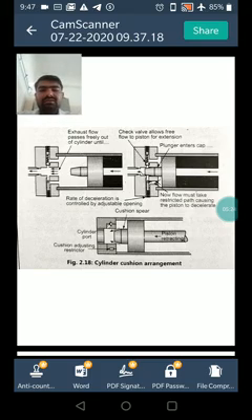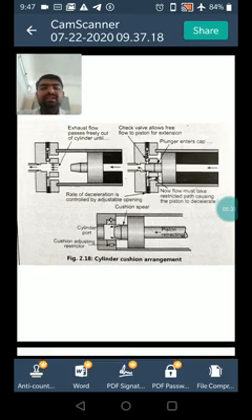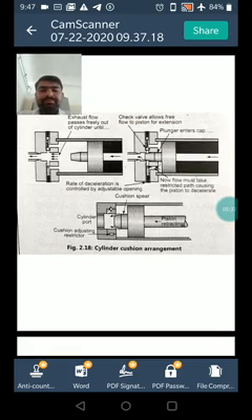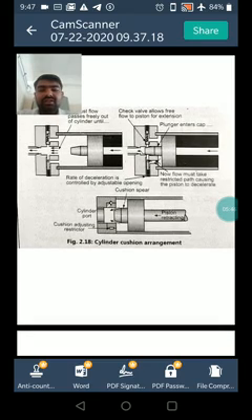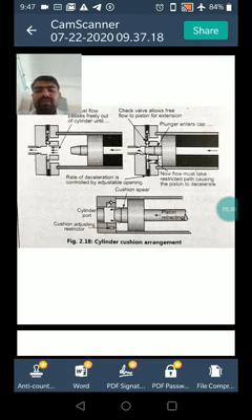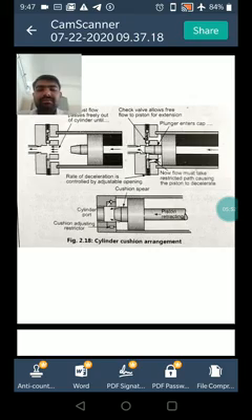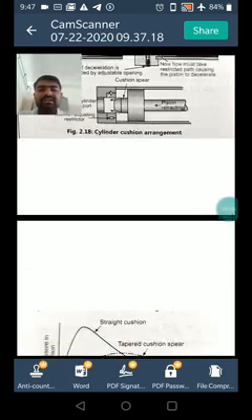The exhaust flow passes freely out of the cylinder, and the check valve allows free flow to the piston for extension. Plunger enters cap. Rate of deceleration is controlled by adjustable opening. This point shows that now flow must take the restriction path, causing the piston deceleration. And the last diagram: cushion spear, cylinder port, cushion adjustment restrictor, and piston retraction.